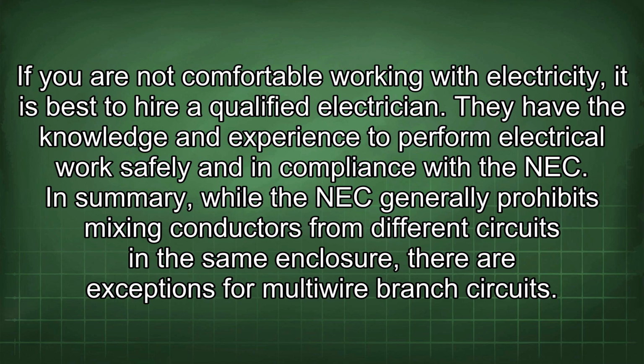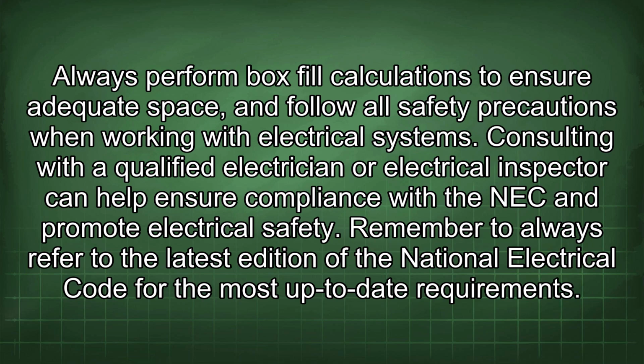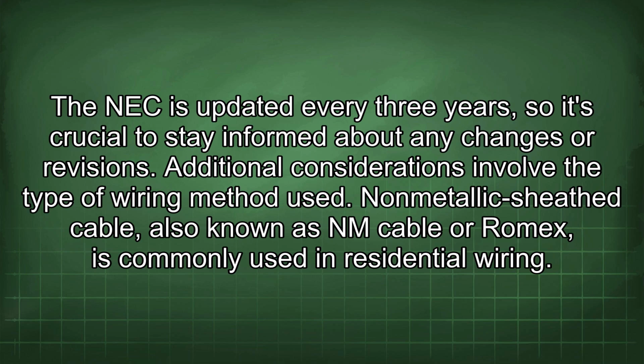In summary, while the NEC generally prohibits mixing conductors from different circuits in the same enclosure, there are exceptions for multiwire branch circuits. Always perform box fill calculations to ensure adequate space, and follow all safety precautions when working with electrical systems. Consulting with a qualified electrician or electrical inspector can help ensure compliance with the NEC and promote electrical safety. Remember to always refer to the latest edition of the National Electrical Code for the most up-to-date requirements. The NEC is updated every 3 years, so it's crucial to stay informed about any changes or revisions.